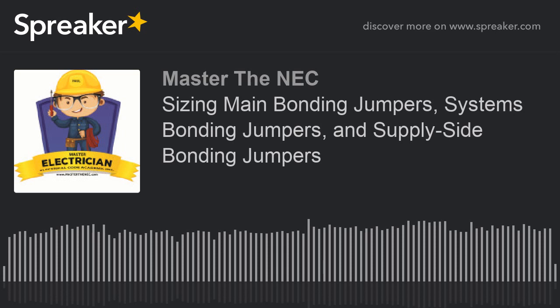All right. First things first, 250.102. It's titled Grounded Conductor, Bonding Conductor, and Jumpers. And it's various jumpers. Supply side bonding jumpers. You'll notice that we use this for the system bonding jumper. We come all the way to 250.102C1. So there's a bunch of jumpers we use. Okay. Main bonding jumpers, all that kind of thing.